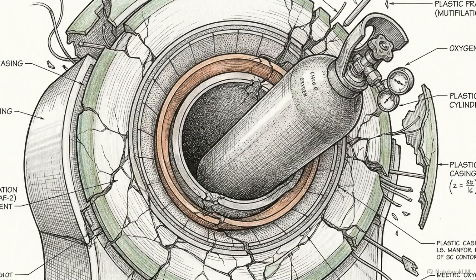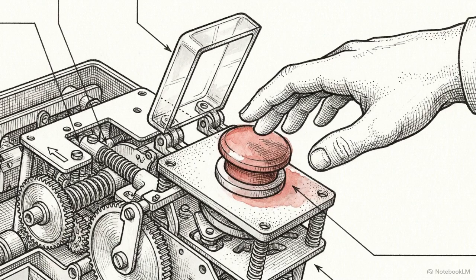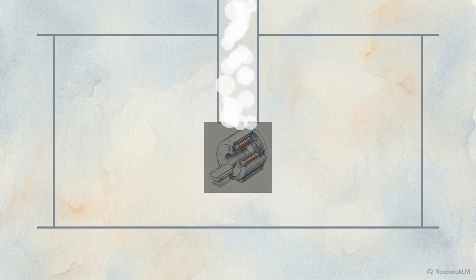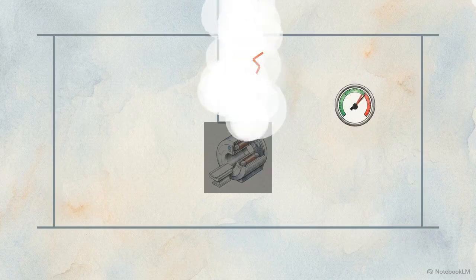If someone is pinned by a metal object, or if a fire cannot be contained, the operator triggers a quench, the rapid decommissioning of the magnet. A quench boils off more than 1,000 liters of liquid helium, instantly stopping superconductivity and eliminating the static magnetic field. The expanding gas vents outside. If a leak occurs, it displaces room oxygen, creating an immediate asphyxiation risk requiring full evacuation. MR safety requires the simultaneous regulation of static pull, thermal energy, and electrical induction. Maintaining these 3 physical forces within biological thresholds is what allows for diagnostic imaging without injury.